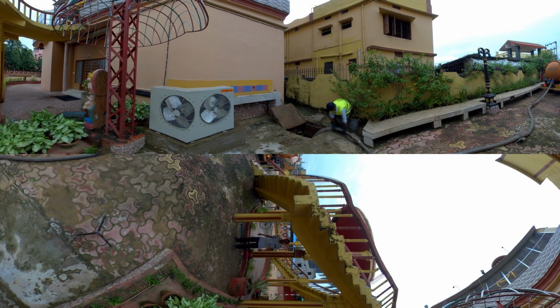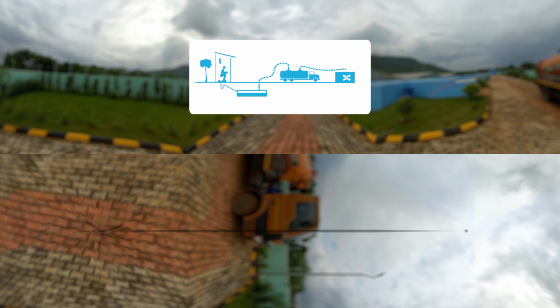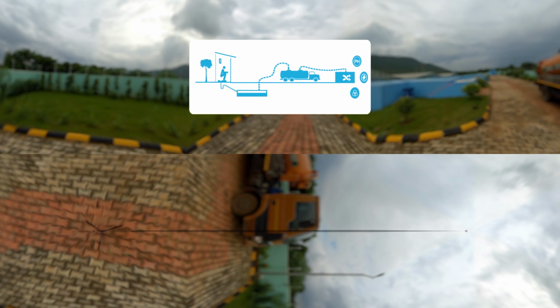Fecal sludge is collected from households and commercial establishments and is then brought to the FSTP for treatment via trucks. FSTPs are not designed to treat industrial wastes, oil-based commercial wastes, etc. Hence, the waste brought by the trucks has to be screened by testing for pH, color and measuring electrical conductivity, based on which the waste can be accepted or rejected.